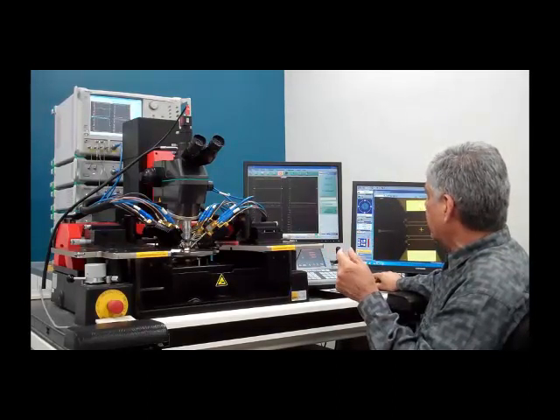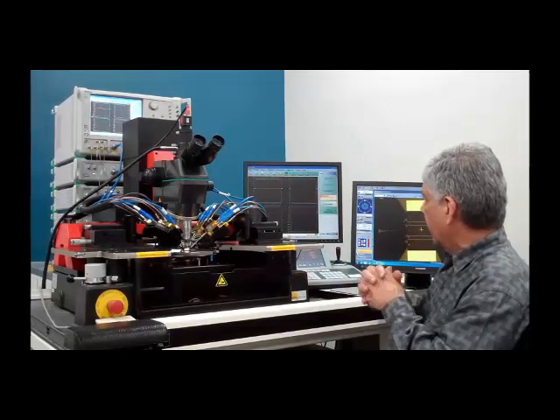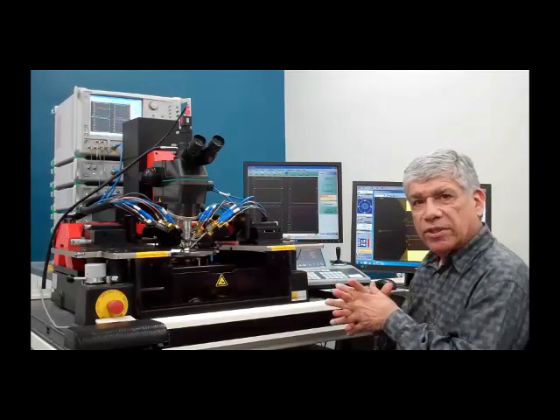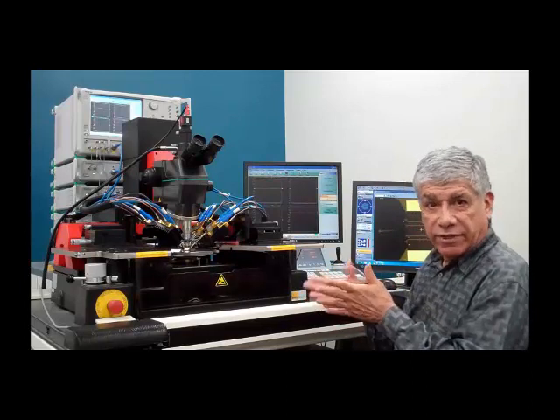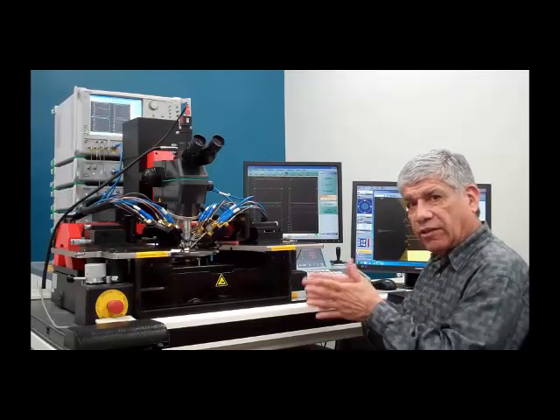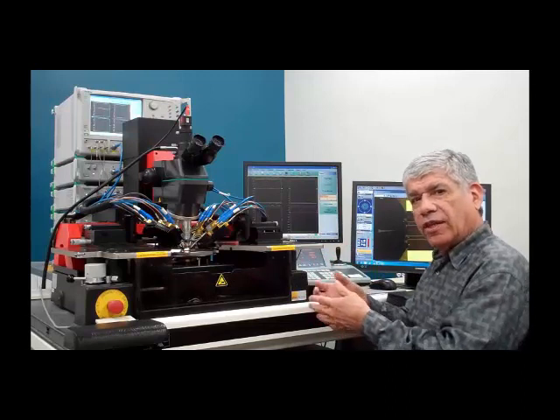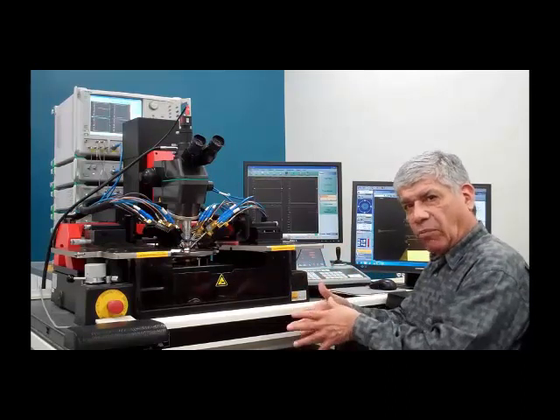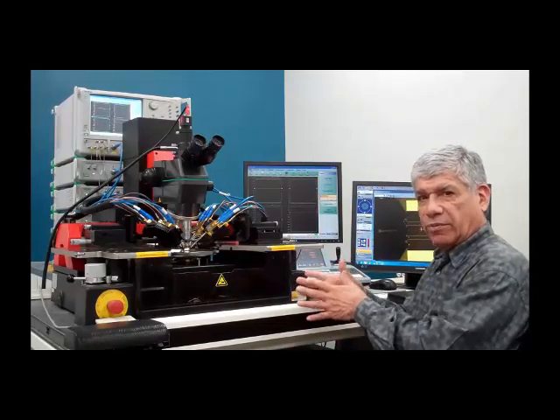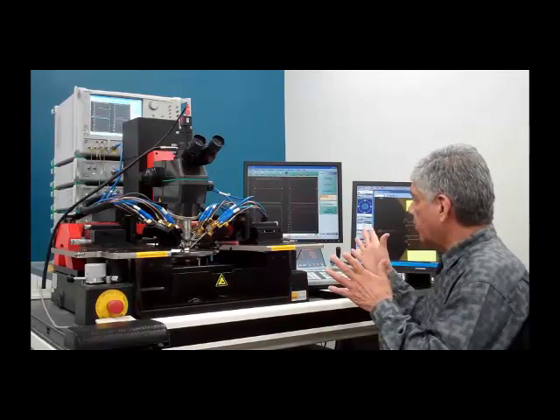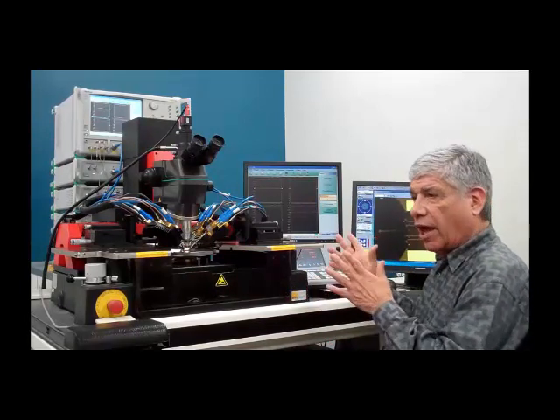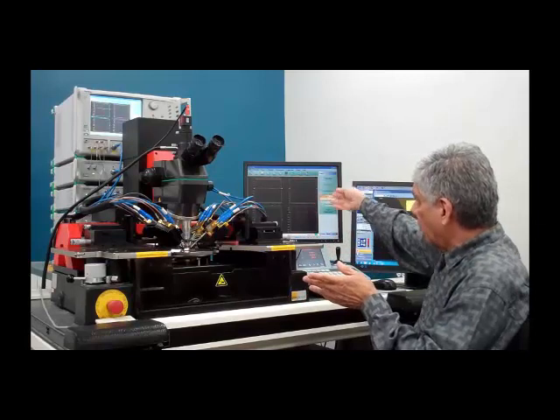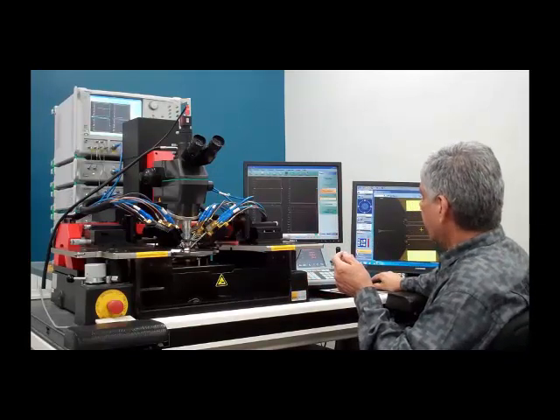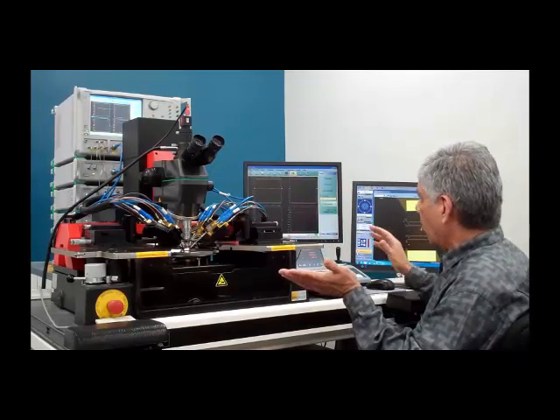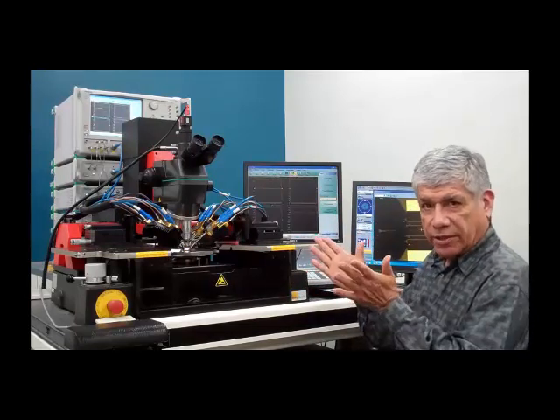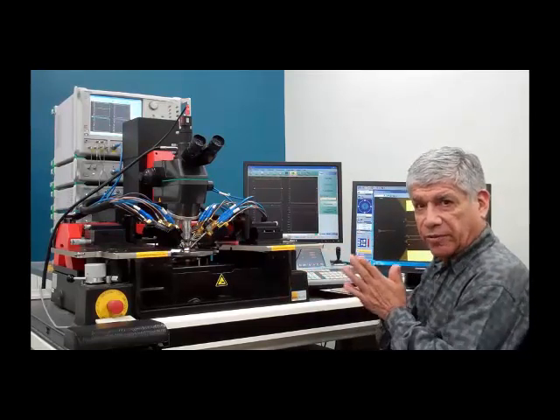And the traces are entered here, and we can go up to 16 traces. We also have 16 channels. So the different channels can be completely new VNA setups with different calibrations, different application measurements, etc. In this case, we're only doing 1 channel and 4 traces for the 4 differential parameters. And that's basically all we need to do to set up the system, getting ready for the measurement.